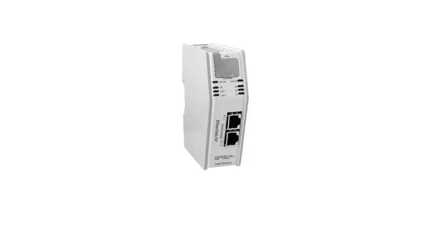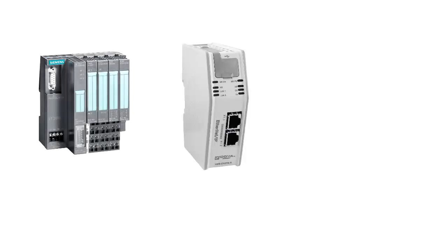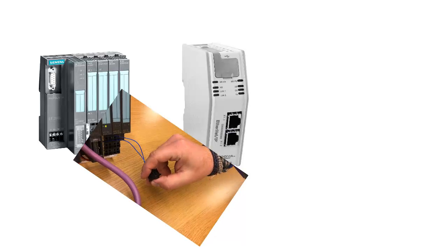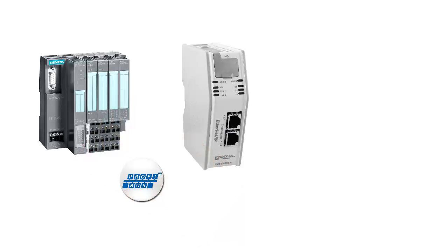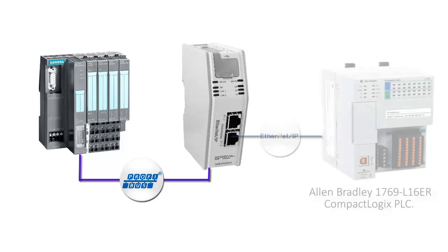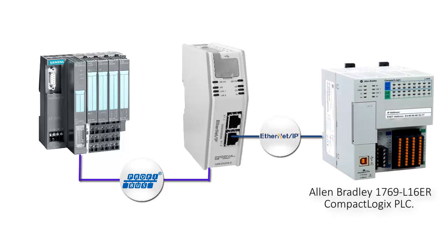In the scenario we're using, I've connected a Siemens ET200S Distributed IO as a PROFIBUS slave. To this, I've connected a simple switch, which gives me an on and off signal. The ET200S is connected to the bottom side of the linking device. On the front side, I'm connected to an Allen Bradley 1769 L16ER CompactLogix PLC.